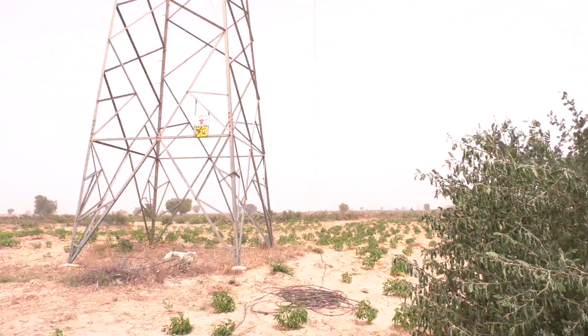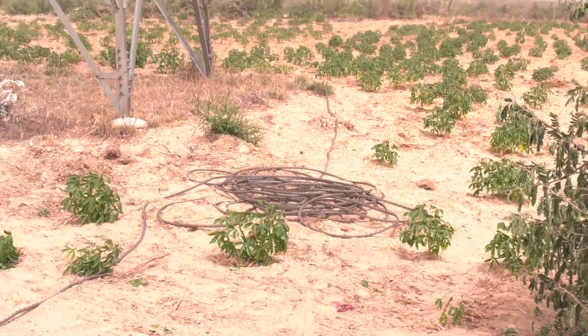This conductor — this material you are seeing here, this wire that is holding — is known as pilot wire. It's a steel material used right from the puller machine to pilot the stringing activity of the job we are doing. The main job of this pilot wire is to enable the machine to take the wire from the tower down to the machine for reconductoring. So it is different from the conductor you see on the tower.